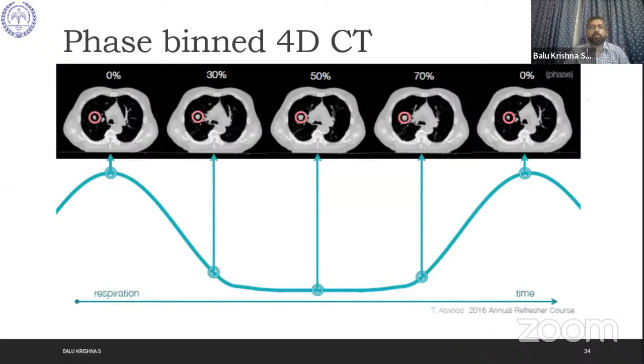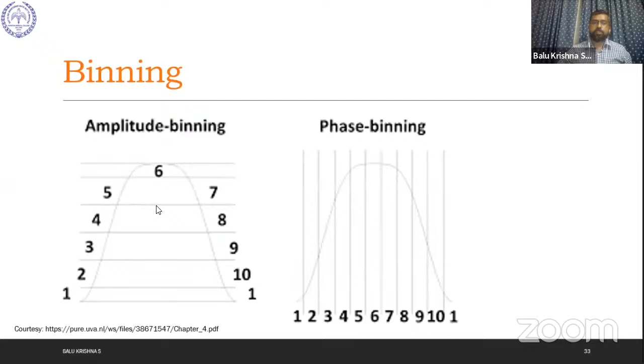So 1000 slices. Now, in a binning process, all the zero phase slices will be binned together to become one CT. Then the 10 percent phase will be binned together. Like that, all 10 phases will be sorted out. That sorting out and reconstructing the CT is called binning. This can be done in the amplitude direction also, which is called amplitude binning.